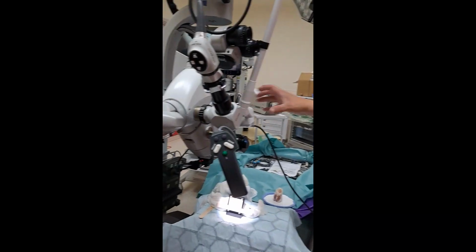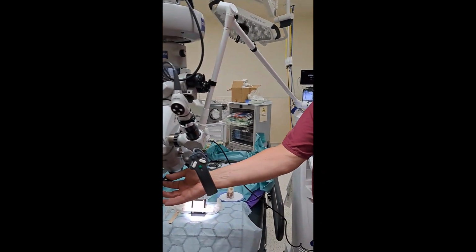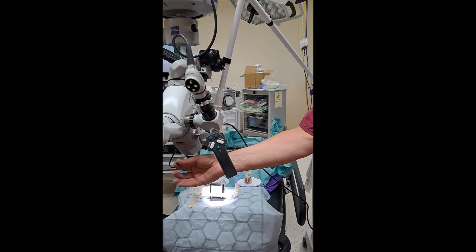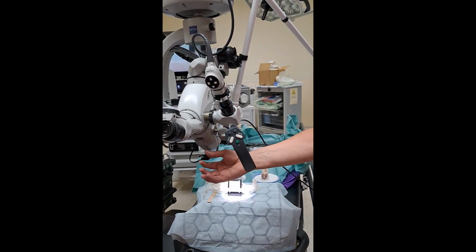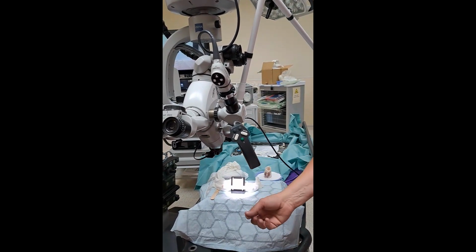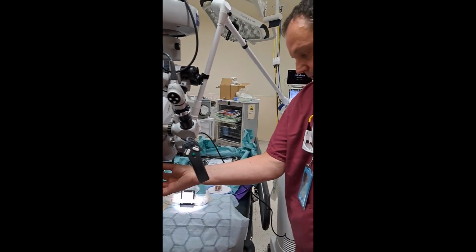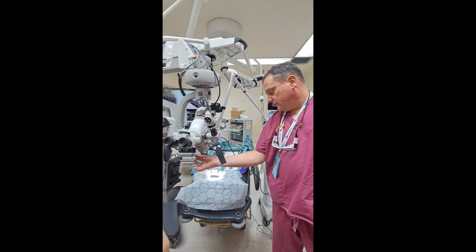When we marry that scanner up to the micro manipulator, this allows the surgeon to move the laser beam in any direction. This has something called a digital AcuBlade, and what that allows the surgeon to do is, if you just manipulate the joystick slightly, change the shape.